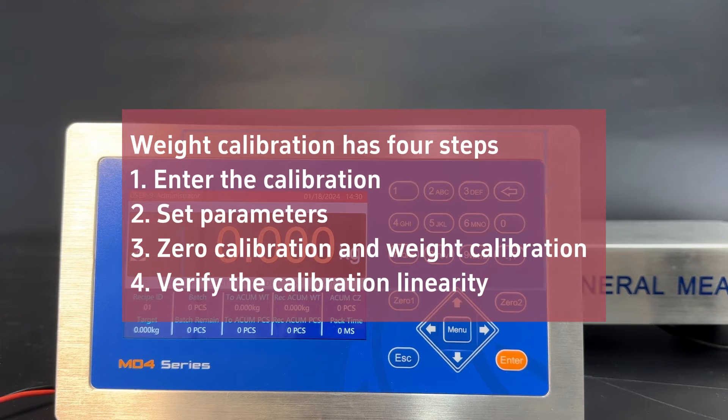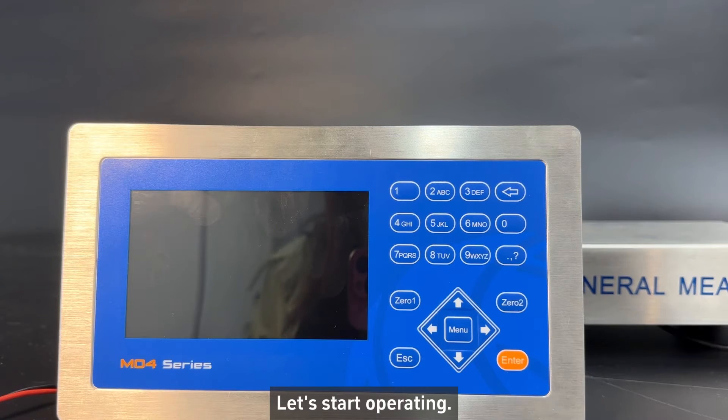1. Enter the calibration. 2. Set parameters. 3. Zero calibration and weight calibration. 4. Verify the calibration linearity. Let's start operating.